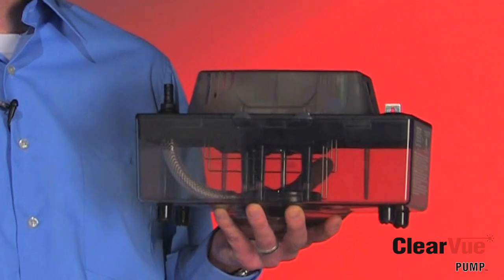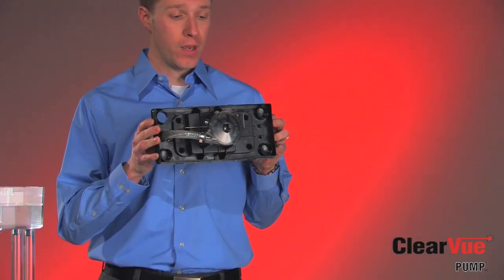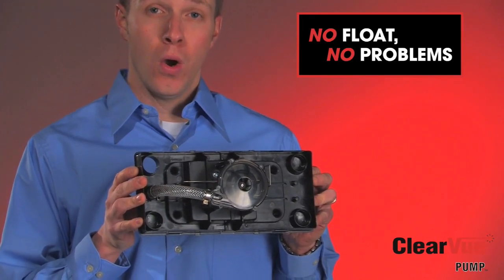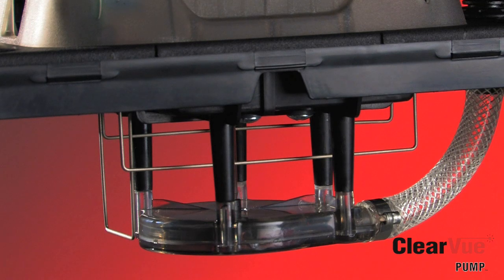But that's not close to the most important feature of this pump. What we've done with ClearVue is we have removed the float. The float is one of the most common sources of mechanical problems in condensate pumps in today's market. What we've replaced the float with is what we call our floatless sensor technology. Floatless sensor technology in ClearVue includes three different stainless steel sensors: the empty sensor, the run sensor, and the high-level alarm sensor.